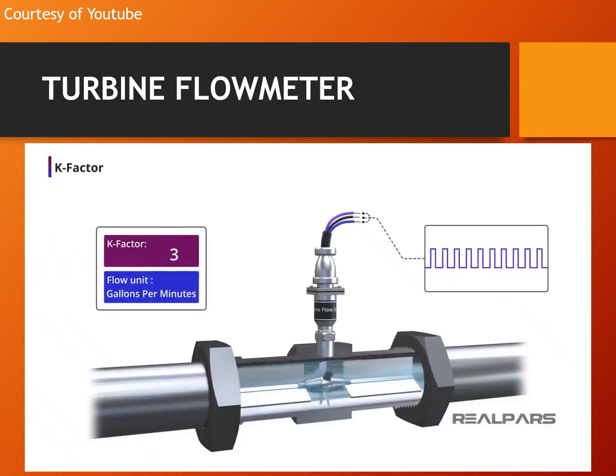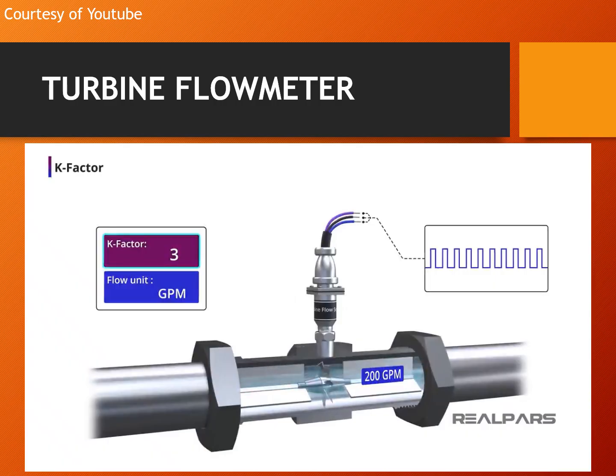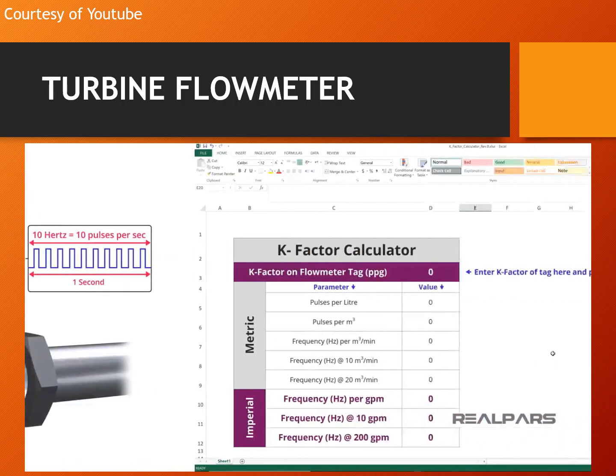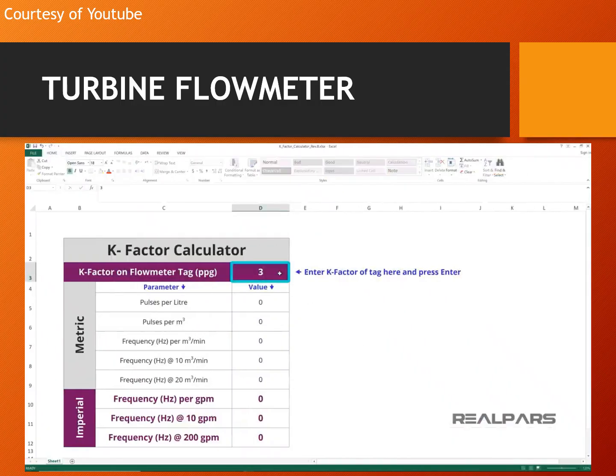Let's assume we are using a turbine flow meter to measure flow in gallons per minute, or GPM. This turbine flow meter has a K factor of 3 pulses per gallon. Recall that the unit for frequency measurement is hertz. 1 hertz is equal to 1 cycle per second. With that in mind, we say that the turbine flow meter produces a frequency of pulses per second, which we express as hertz. If we have a K factor of 3 pulses per gallon, the output frequency at a volumetric flow rate of 200 gallons per minute, or GPM, is 10 hertz, or 10 pulses per second. If you're wondering where we derived these values, we've included a very handy K factor calculator for you to use. You can find the link to this K factor calculator file in the video description.